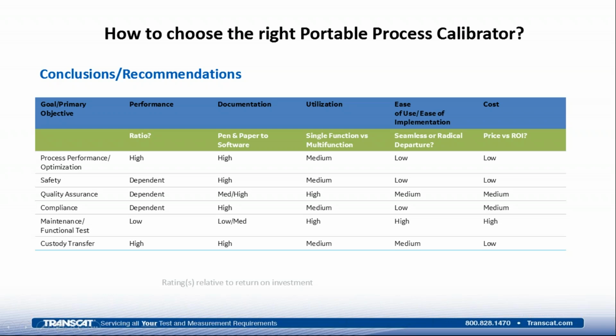A possible consideration, a suggestion, a recommendation: defining a selection matrix, helping tie together the goals and primary objectives to the approach or criteria for selection. So, for example, if we're looking at process performance improvement or optimization, obviously the performance of the calibration equipment is going to be very high, right? If we're looking at the maintenance or functional test capability, where we're just trying to determine if something's working or not working, performance may not be as much of an issue.